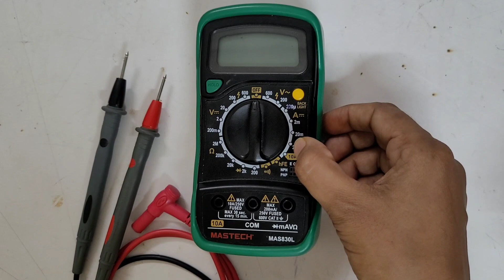The 10A port, that is 10 ampere, is the special port used when measuring large currents greater than 200 milliampere, because the other port measures currents in milliampere, so there the maximum we can measure is 200 milliampere.